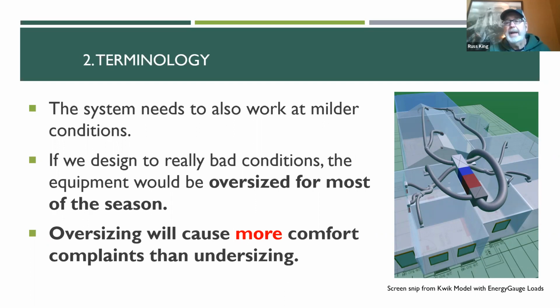And what happens is if you size for too extreme of a temperature, on those mild days, the system will be way oversized and you'll actually have comfort issues on the mild days, which seems kind of weird, but it's true. If an air conditioner is oversized, it does what's called short cycling. It turns on and off too quick. You never reach the full capacity of the equipment.